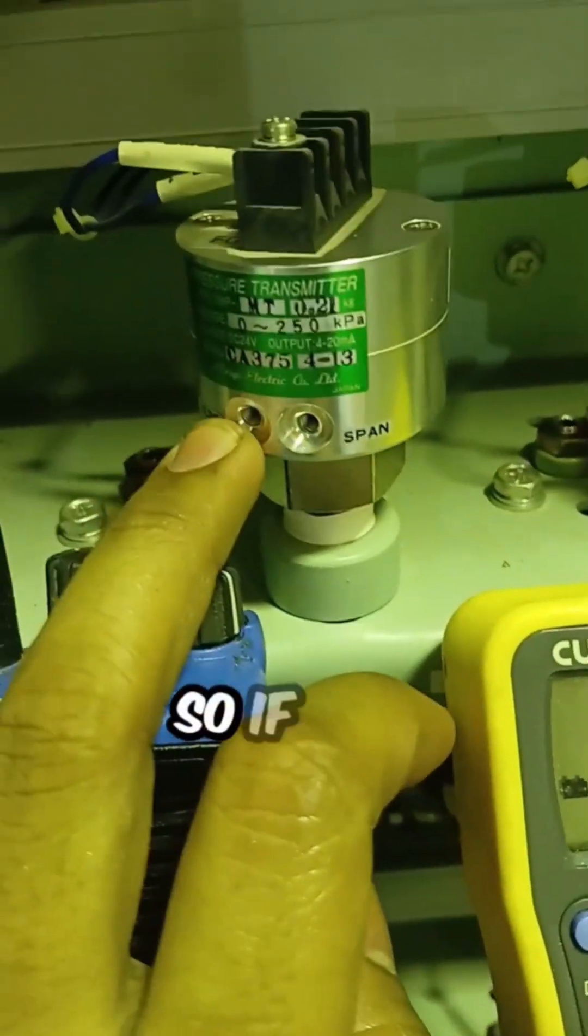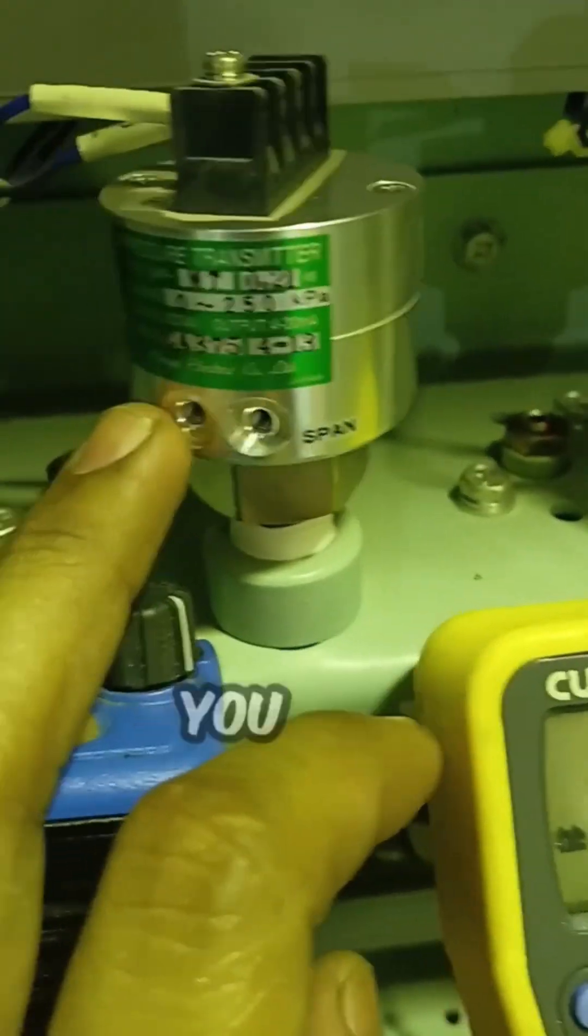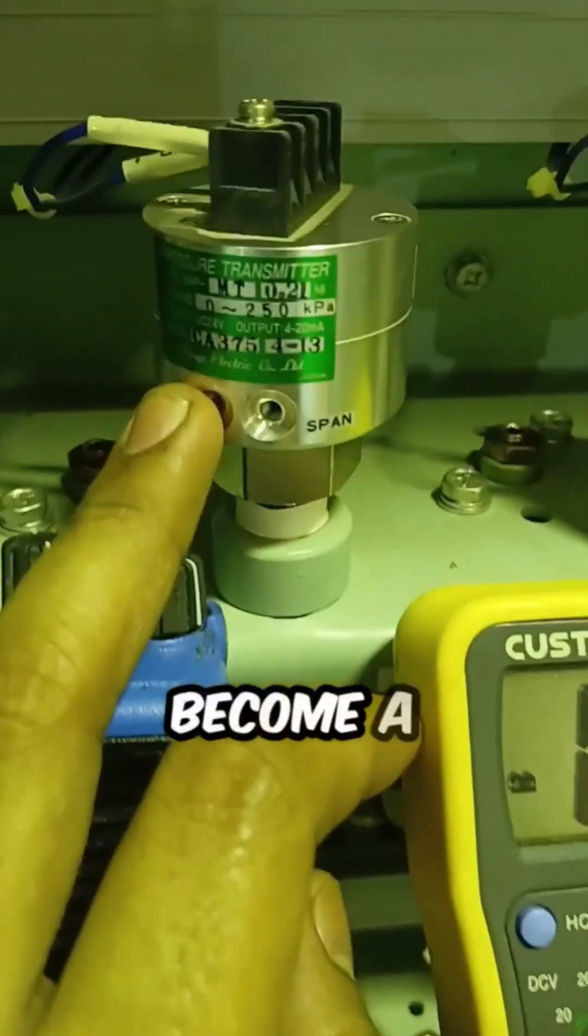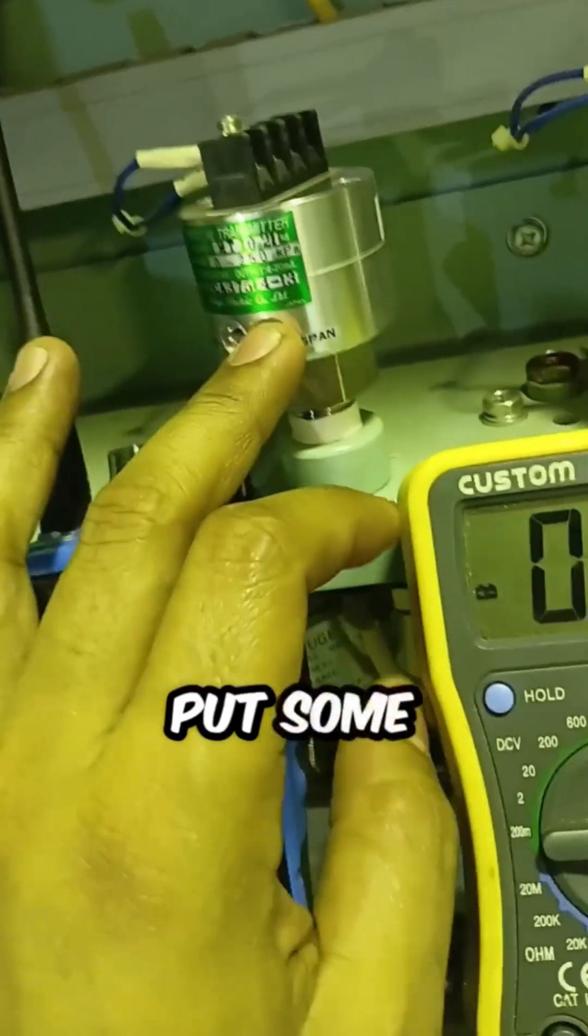So at zero pressure, like while removing the pressure, you will get 4 milliamp. So if not get 4 milliamp, like before you get 3.5, you can adjust and make sure you become 4 milliamp.